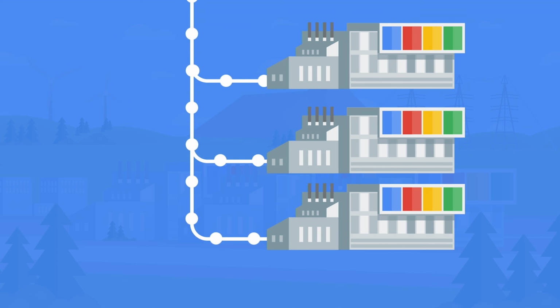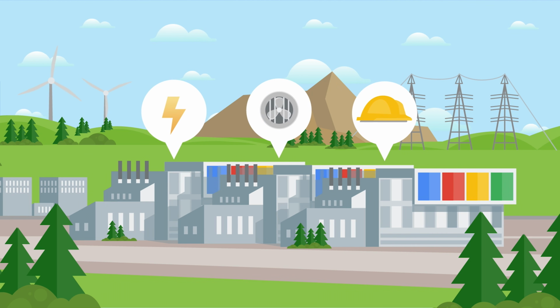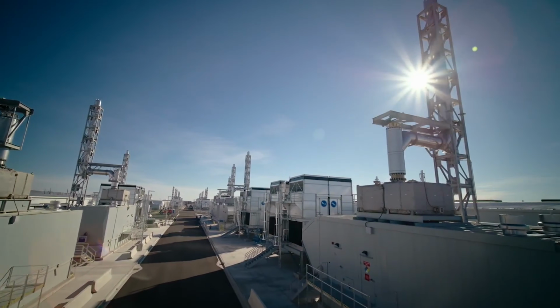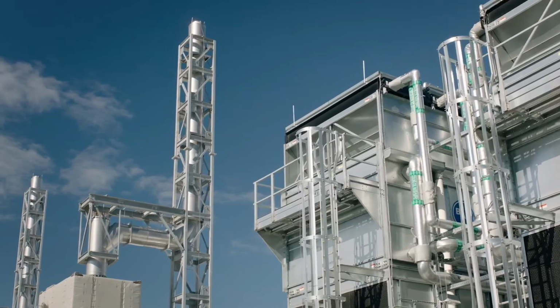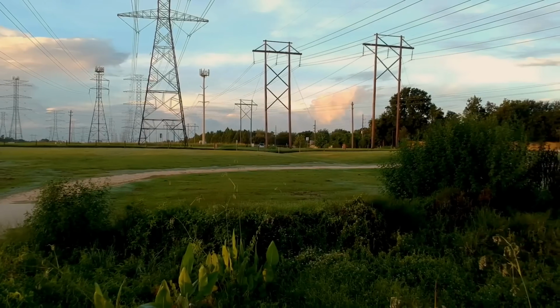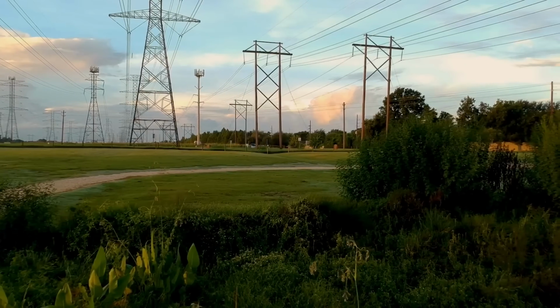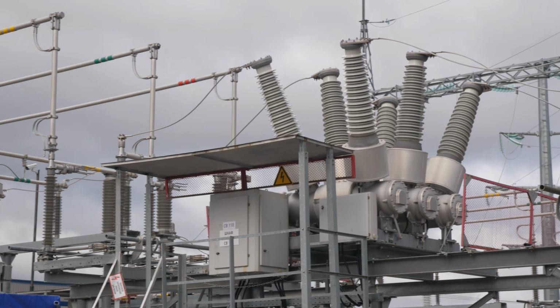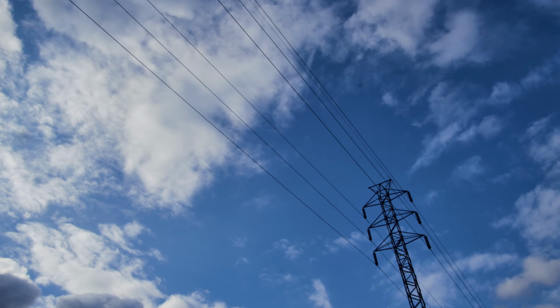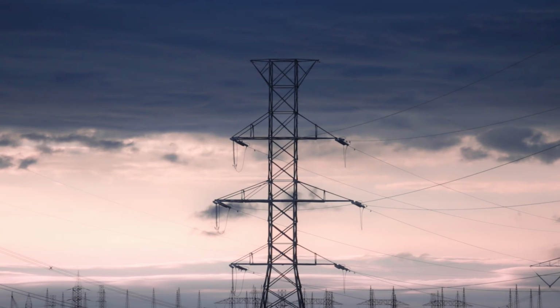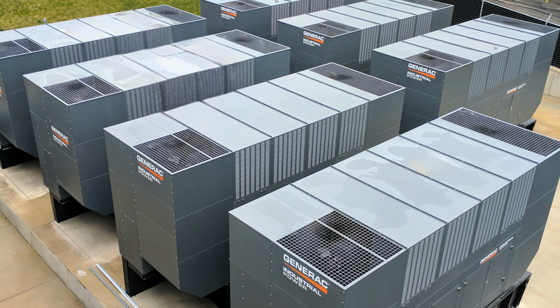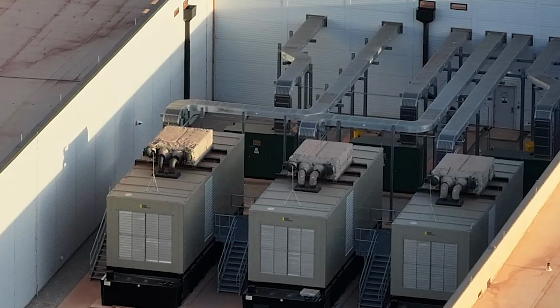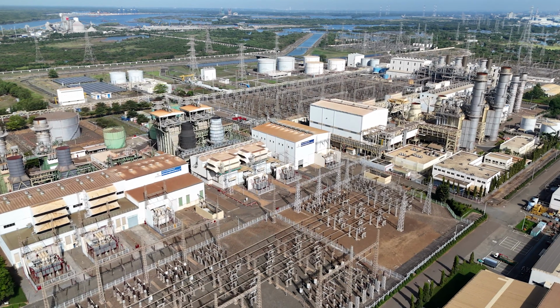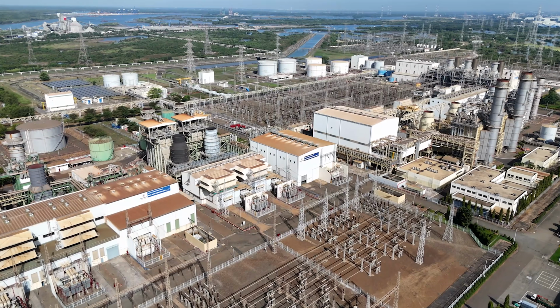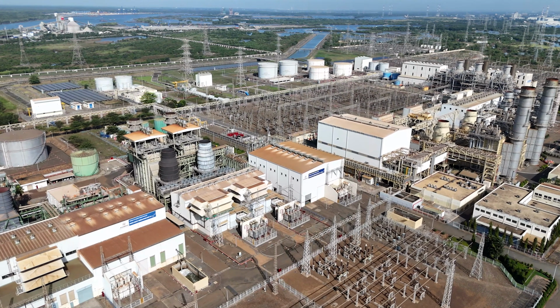Every data center runs on electricity. Not a little electricity, a lot of electricity. A 100 megawatt facility consumes roughly the same amount of power as a small city. Getting that power to a site requires utility-grade electrical infrastructure: high voltage transformers, switchgear, which is the equipment that controls and protects incoming high voltage power before it reaches the facility, redundant feeds from the grid, backup generators with enough diesel capacity to run the facility for days during an outage, and uninterruptible power supply systems that bridge the gap between a grid failure and the generators coming online.